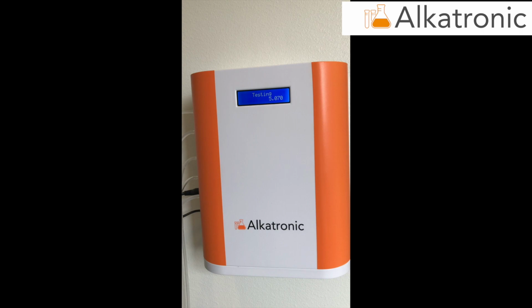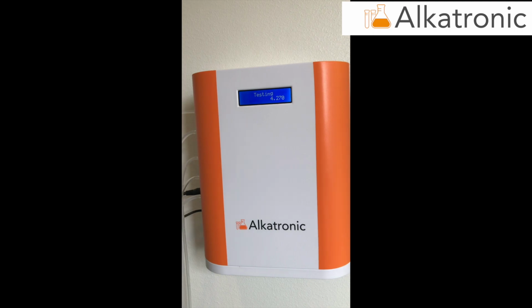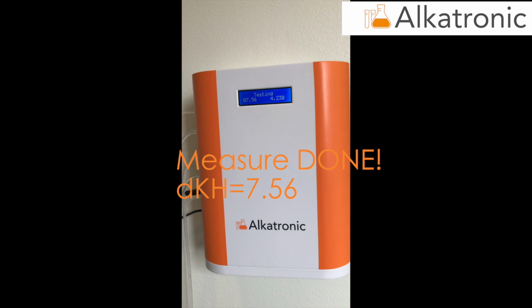The measuring phase is also followed on the LCD display, and you see figures to the right. The figures to the right are not the KH, it's the pH, which indicates that the process is correctly performed. And there we have the measurement ready. 7.56 DKH is the result, and now the machine will go through some rinsing phases, etc. And after that we will have a standby display with the actual DKH measurement, and the machine will do any actions from that.